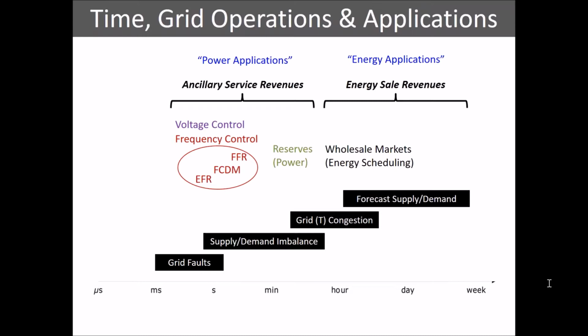It's things like faults in the grid, a power line gets struck by lightning. It's about unplanned losses of supply. A power plant, a turbine breaks and it goes offline and suddenly you lose a few hundred megawatts of supply. And those kind of very short-term imbalances create challenges, particularly system-wide around frequency. So in Europe, at least, our grid runs at 50 hertz. If you're in the States, it'll be 60 hertz.